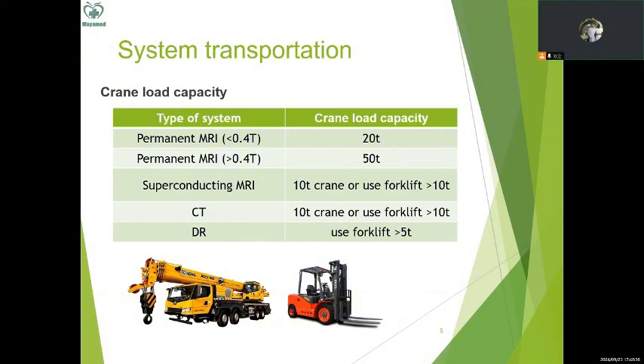For permanent MRI less than 0.4 Tesla, the crane load capacity should be 20 tons. For permanent MRI more than 0.4 Tesla, such as 0.5 Tesla, the crane load capacity should be 50 tons. The superconducting MRI, because the magnet weight is less, needs a 10-ton crane, or we can simply use a forklift. In the right picture, a forklift of more than 10 tons transports the system.